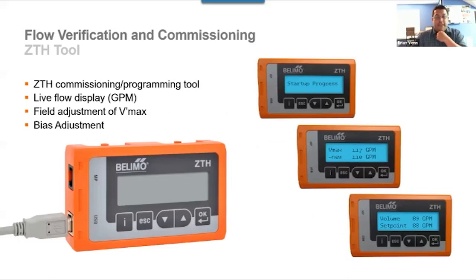And Bob, this is where we actually ran into that when we first came across these valves. As field verifiers, in this case, we needed to learn how to work with a new technology, right? We really needed to dig into the cuts and understand that it was factory set, and there was a reason it wasn't going to full open. But we didn't understand it until we really dove into the technology. And once you do that, there is a little bit of retraining for your workforce on the TAB side to adjust to this, but we're constantly going to be doing that as technology evolves anyway. So for us, we had a couple of hard learning lessons, but then we were able to understand the valve after 1 or 2 jobs. And now they're a welcome sight, because we are not losing our traction as balancers. We're still verifying. And when troubleshooting occurs, we really are the experts there to figure out what's going on anyway. So it's a good measure to still have trained TAB folks doing the verification. Yes.